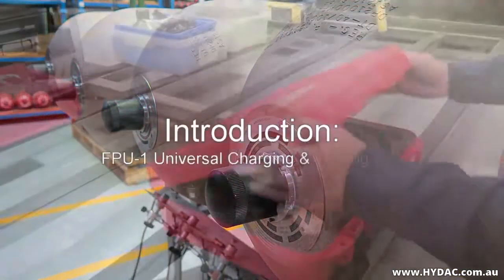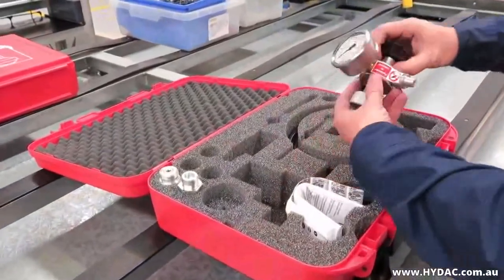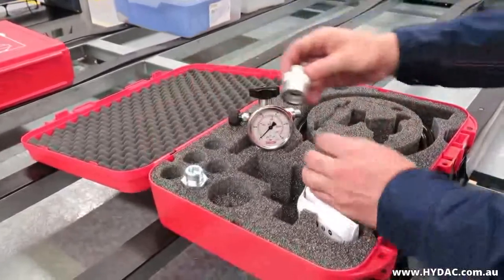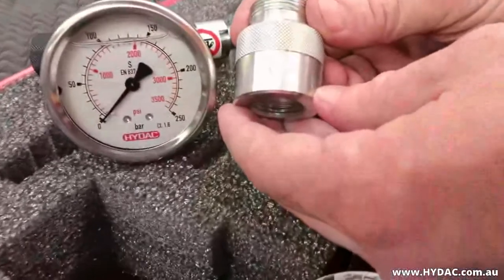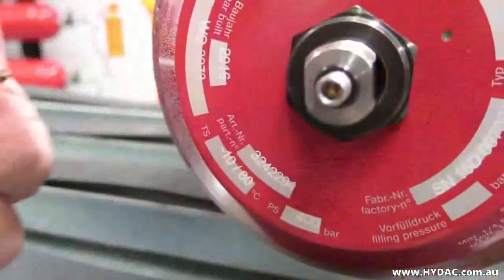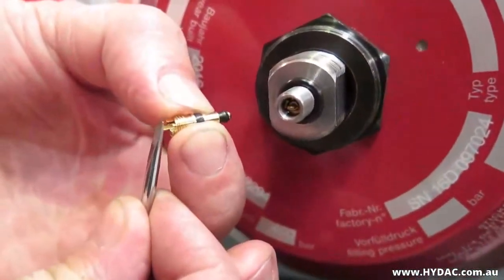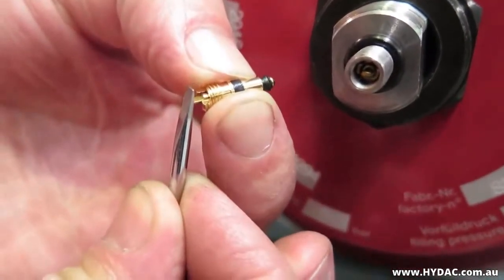The HYDAC FPU1 universal charging and testing unit can be fitted directly to HYDAC diaphragm and piston accumulators, but it uses an adapter to connect to a bladder type accumulator. This is known as the A3 adapter — it is clearly stamped A3. The accumulator gas valve will be opened and closed by pushing the valve plunger down, which will be operated by the centre screw of the A3 adapter.